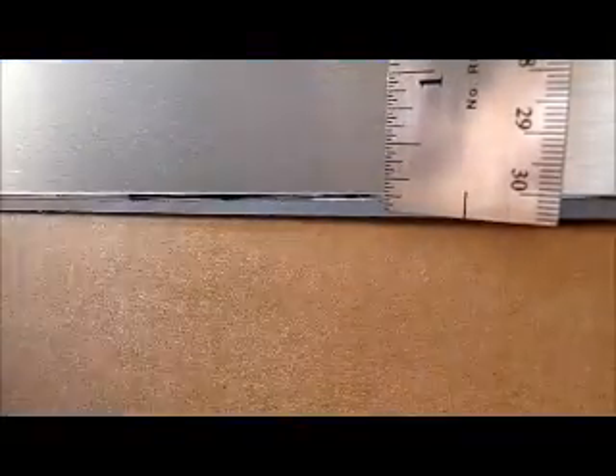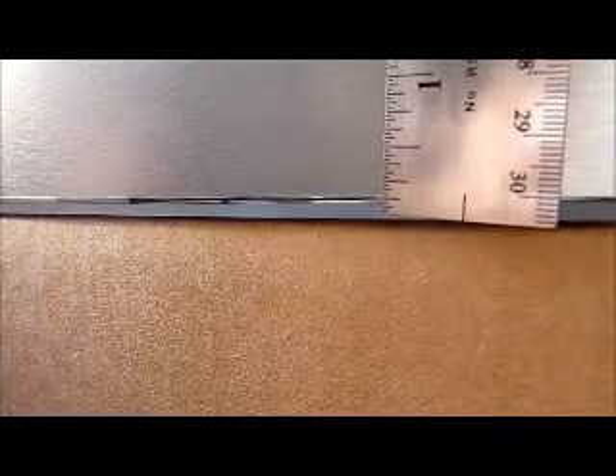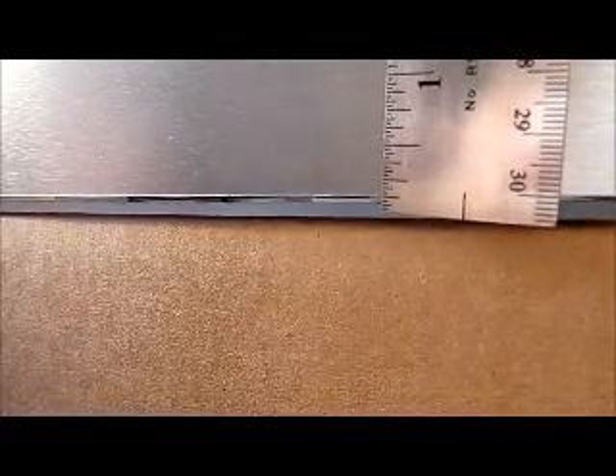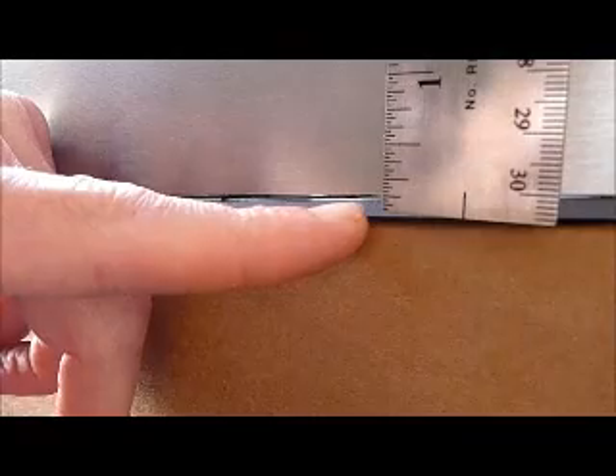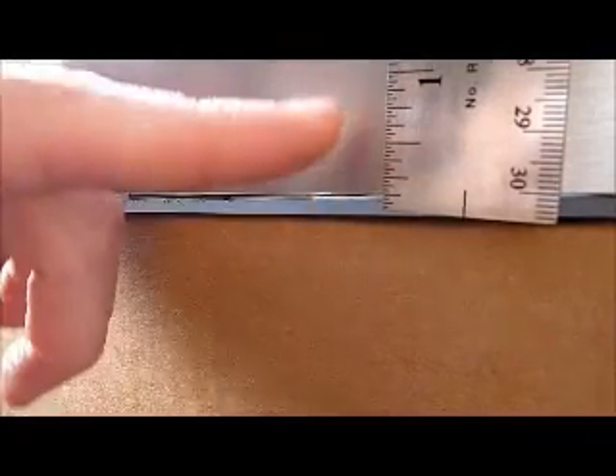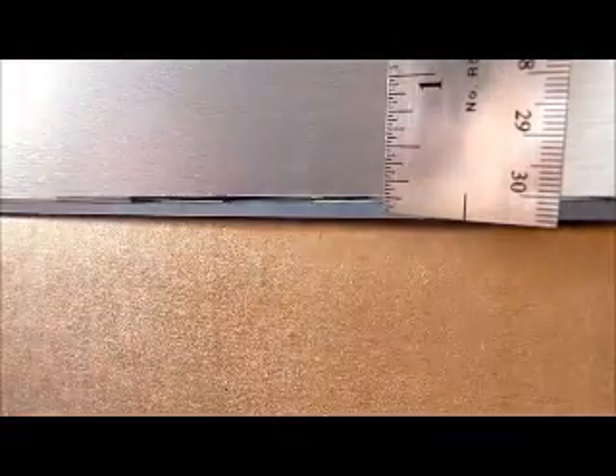Next thing you want to do is check to make sure you're not constricting the hot air exit from the side of the fixture. Hot air will exit through the side of the fixture between the acrylic shield and the side of the housing itself. And ideally, this gap should be 1/4 inch.